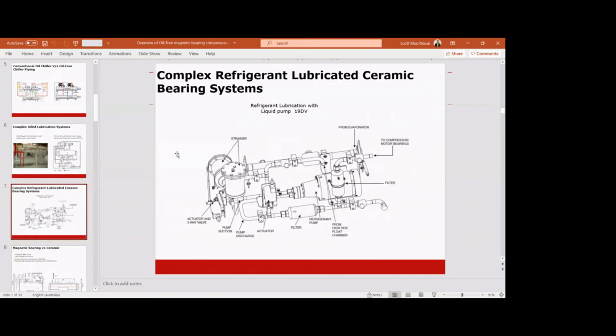On the ceramic bearings, as we explained before, we have to pump liquid onto the bearing assembly inside the compressor. And so the pump arrangements are very complex and very expensive for ceramic bearings. So it's not just as simple as running a set of ceramic ball bearings. We have to pump liquid refrigerant onto the bearings to keep them cool enough to run. And as you may understand, these low pressure machines on R1233 are very big in dimension and very heavy.